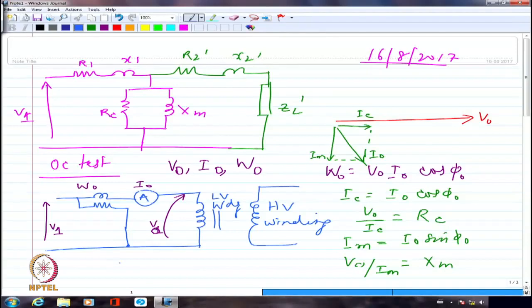What I could have shown is directly applying it through a variac, and the variac in all probability will be connected to the top point. No isolation. The open circuit test does not require isolation. But if I am plotting a BH loop, because I am connecting the power components directly to the CRO, and the CRO is meant only for electronic components, not meant for power components, I'm mingling the two. I better take precautions.